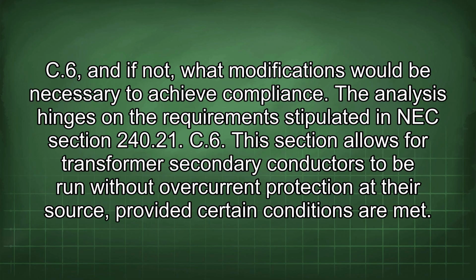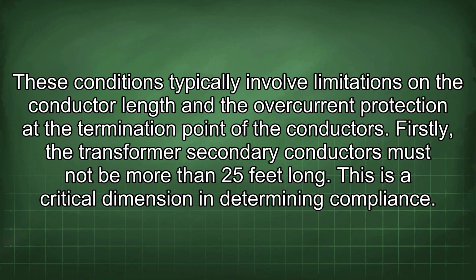The analysis hinges on the requirements stipulated in NEC section 240.21(C)(6). This section allows for transformer secondary conductors to be run without overcurrent protection at their source, provided certain conditions are met. These conditions typically involve limitations on the conductor length and the overcurrent protection at the termination point of the conductors. Firstly, the transformer secondary conductors must not be more than 25 feet long. This is a critical dimension in determining compliance.